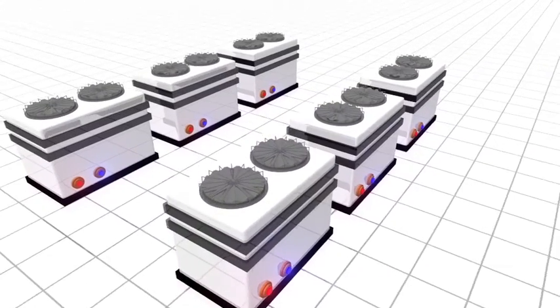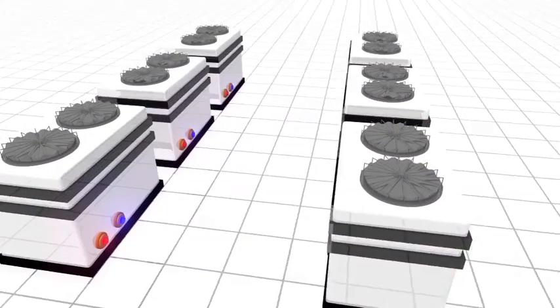Now we looked at hot aisle containment, we looked at cold aisle containment and realised that hot aisle containment was the only way that we were going to be able to achieve this in the data centre. With the hot aisle containment we were able to raise our chilled water temperature.